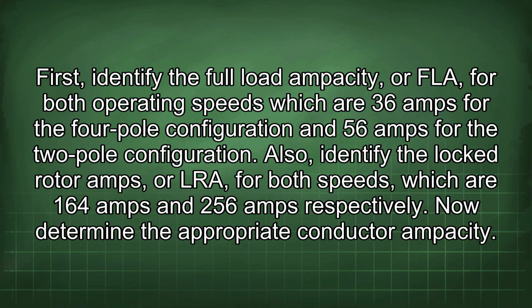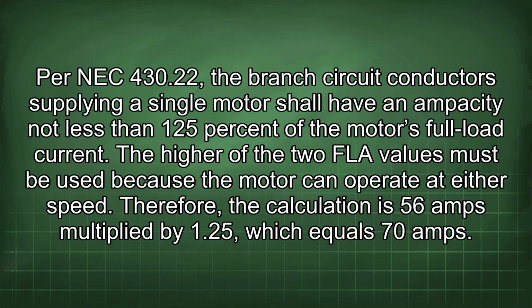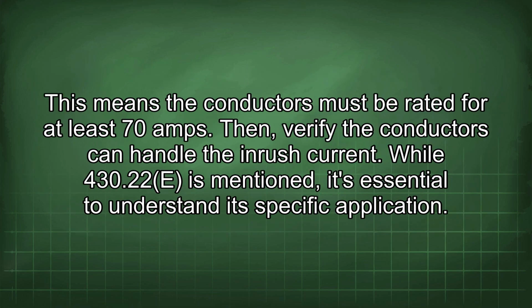Now determine the appropriate conductor ampacity. For NEC 430.22, the branch circuit conductors supplying a single motor shall have an ampacity not less than 125% of the motor's full load current. The higher of the two FLA values must be used because the motor can operate at either speed. Therefore, the calculation is 56 amps multiplied by 1.25, which equals 70 amps. This means the conductors must be rated for at least 70 amps.